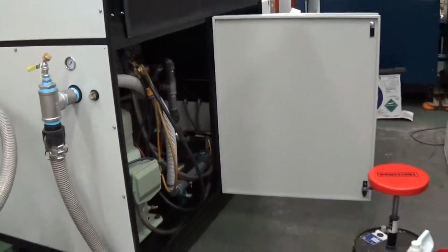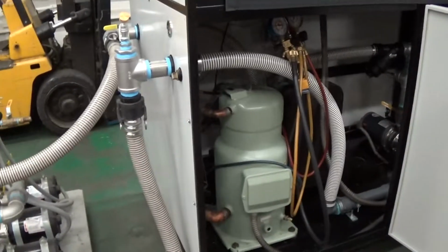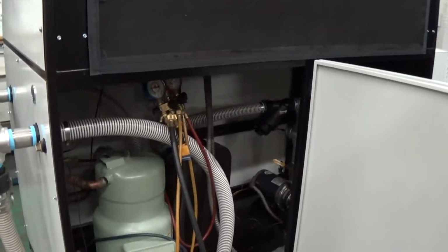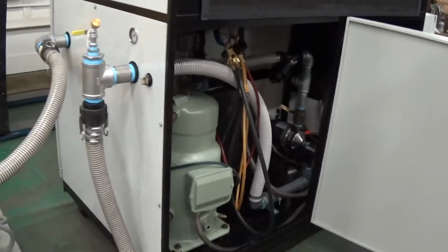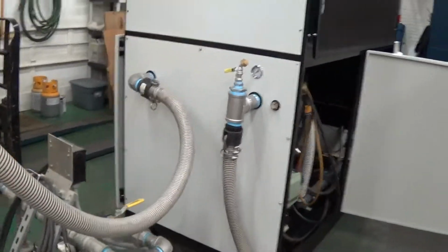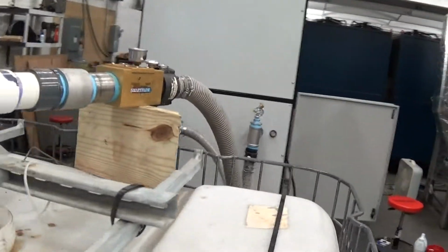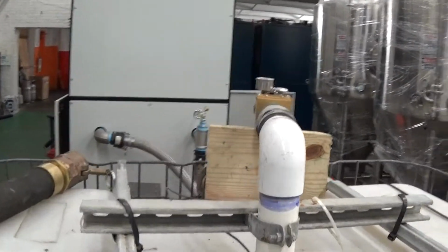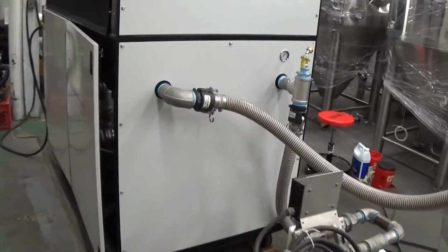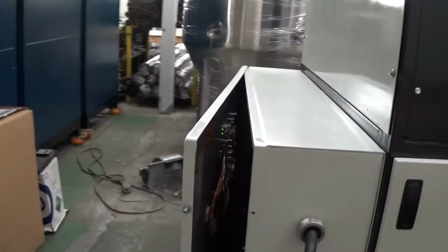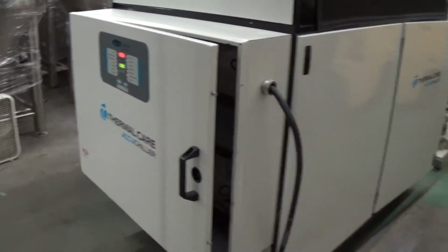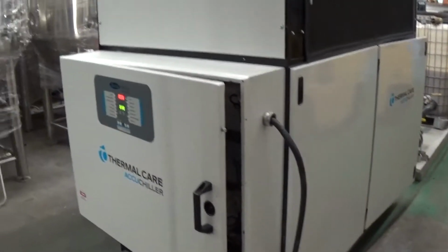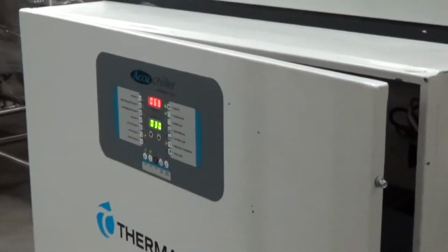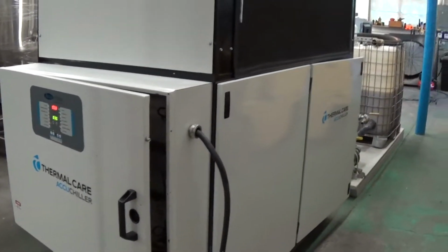Once we reach a lower set point like this that we're running, the unit does have a hot gas bypass option, which is capacity control. The idea there is to leave the compressor running as long as possible within reason, because we don't like frequent starts and stops on compressors. So you'll start hearing a hissing noise when you're running at these lower temperatures and with such little load. Our load is just the tank. You can see we're already down 5 degrees or so. You're going to hear that hissing, and it's going to be maintaining at the 30.